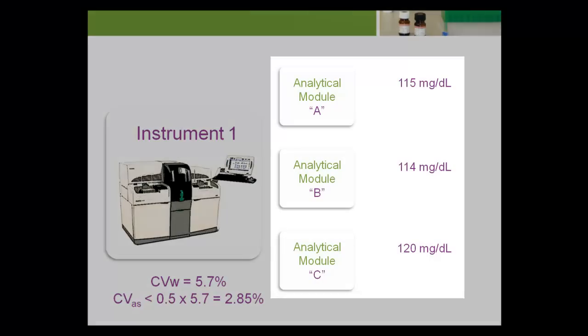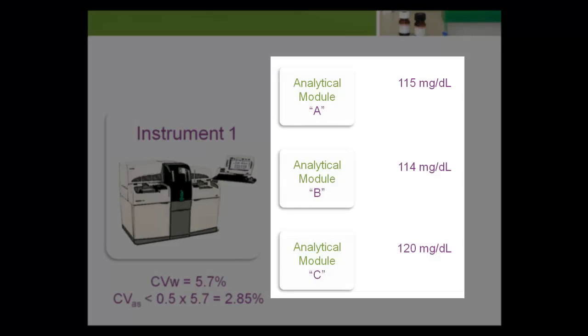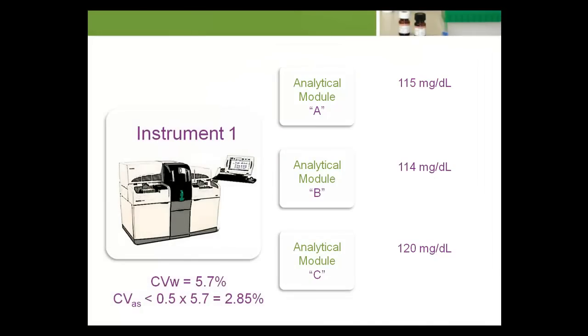Each module tests approximately one-third of the glucoses ordered on patient samples. F1 equals F2 equals F3 equals one-third. The mean glucose levels for the three modules based on repeated testing of a quality control material are 115 mg per deciliter, 114 mg per deciliter, and 120 mg per deciliter, and the standard deviations are 3.0 mg per deciliter, 3.1 mg per deciliter, and 3.1 mg per deciliter.